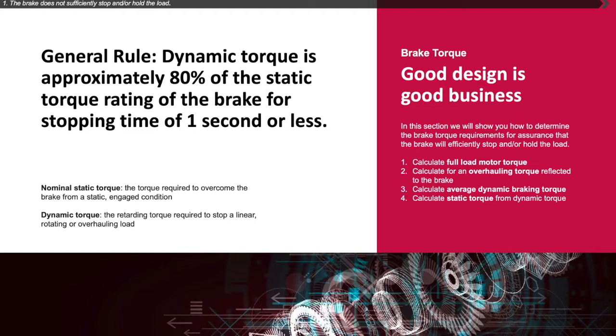Dynamic torque is the torque required to stop an inertial load and is approximately 80% of the static rating. This could be used in linear, rotating, overhauling, or overhung applications, as in the case of a hoist or winch. Calculating proper dynamic torque will guarantee that your brake will not only stop your load, but also stop your load in time to protect all of the equipment within your drive.